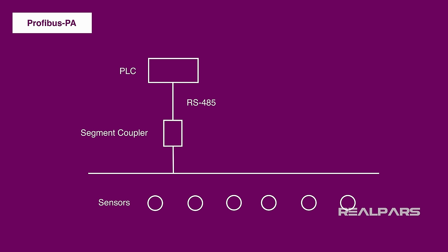With the new setup, instead of connecting the sensors to the IOs one by one, you can connect all of them to a single Profibus PA bus. On the other side of this bus, the segment coupler works to convert the Profibus PA signal to the Profibus DP signal. So by utilizing Profibus PA, you can have an even more economical and more efficient network structure.